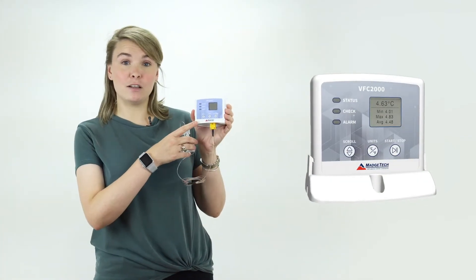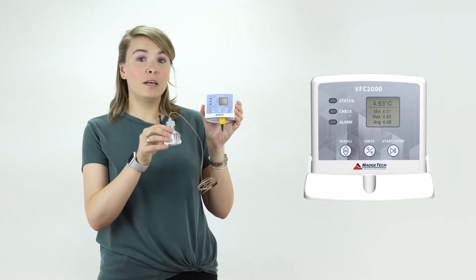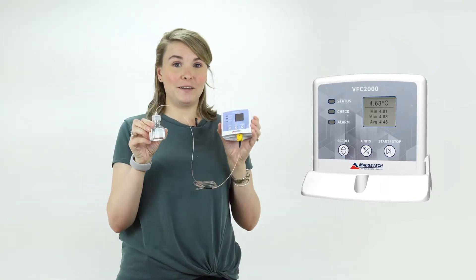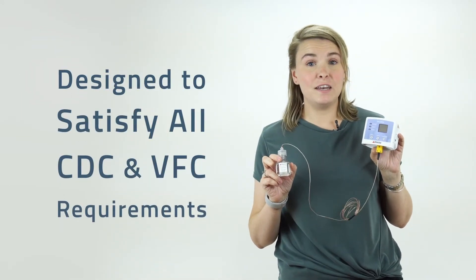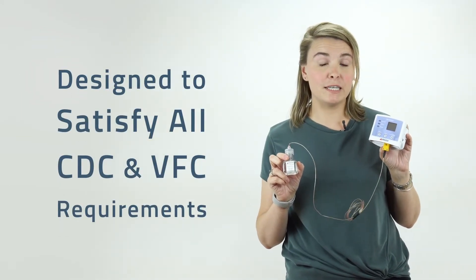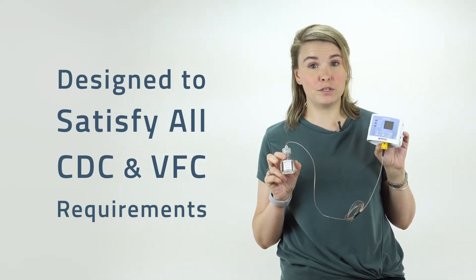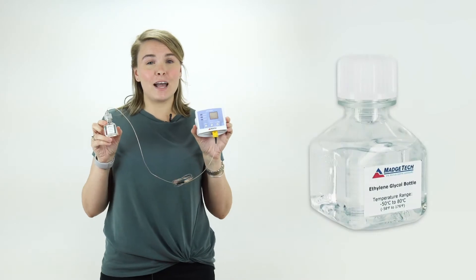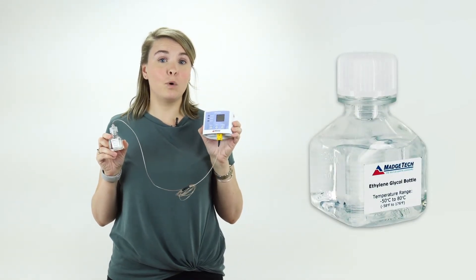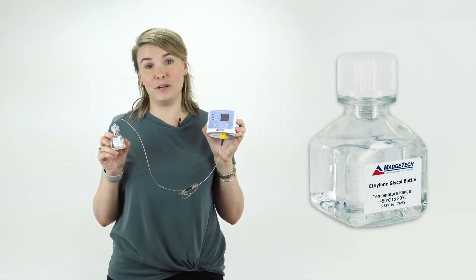It includes a temperature data logger, Type-K thermocouple, glycol bottle, and power supply. The VFC-2000 is specifically designed to satisfy all CDC and VFC requirements for monitoring temperature-sensitive vaccines and pharmaceuticals in fridges, freezers, and coolers. By using the glycol bottle, the device is able to more accurately mimic what pharmaceuticals and vaccines are experiencing.